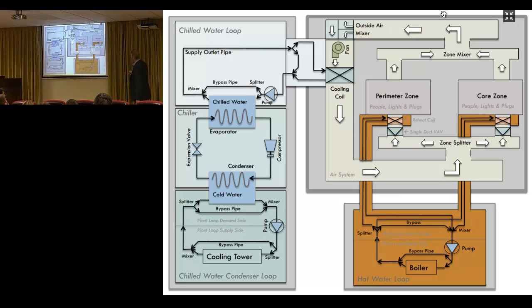And so that's what you see here. You can see air being distributed to these zones. They're the same thing. And what do we do with the air? We return it. We don't throw it all away, because if we want to have 24 degrees Celsius here in the summer, we might deliver air at about 20, and return it at 24. We are not ejecting that air to the 42-degree Sevilla afternoon environment.